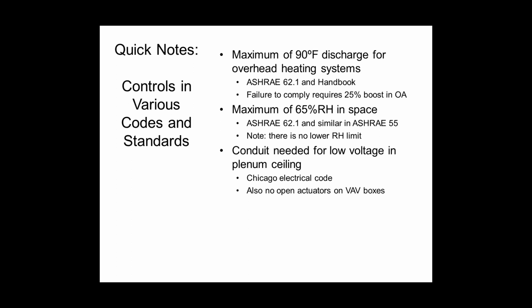In the city of Chicago, specifically, low voltage wiring in the plenum ceiling has to be in conduit. Nowhere else in the world does it seem to be required that way, but in the city of Chicago, if you want to run 24-volt control wiring through the ceiling cavity, you have to put it in conduit. It's not a big deal. It's not hard to do, but it does change how you bid the labor on your project.